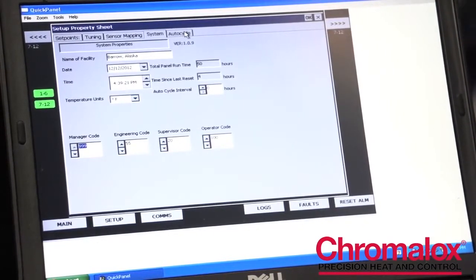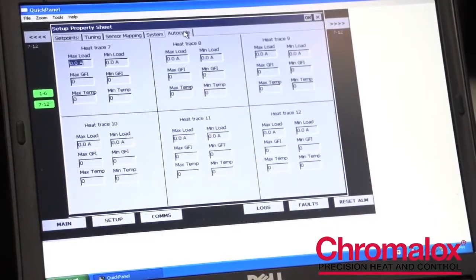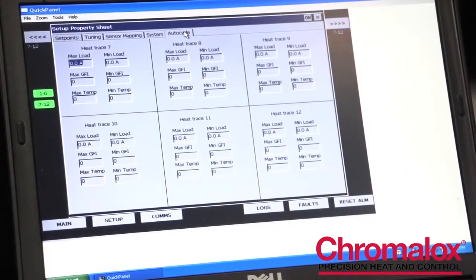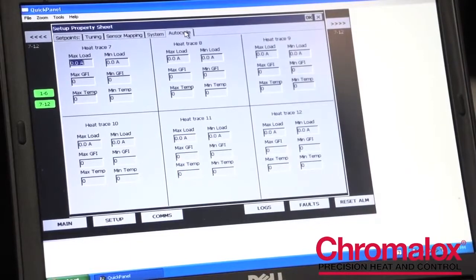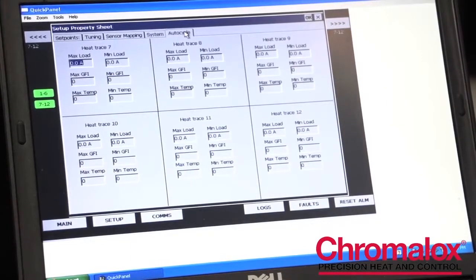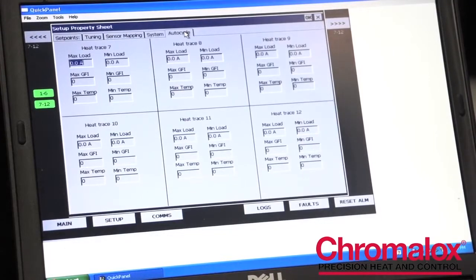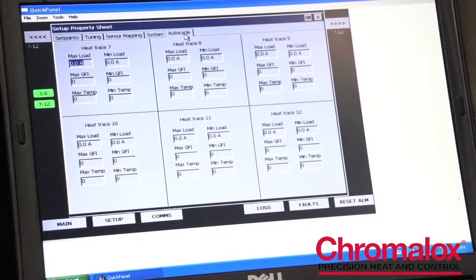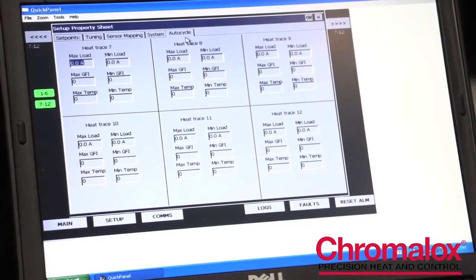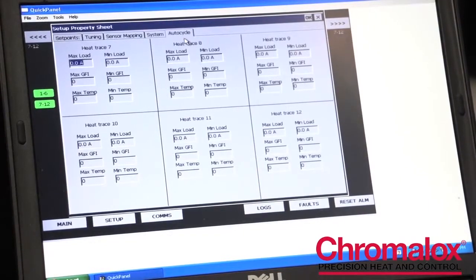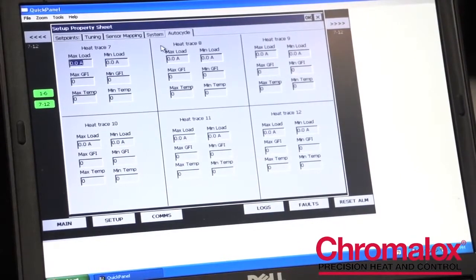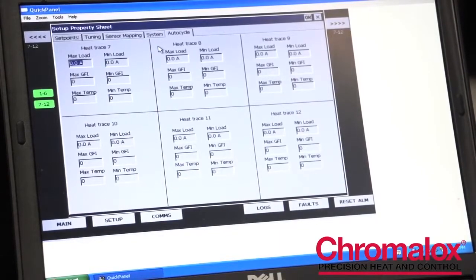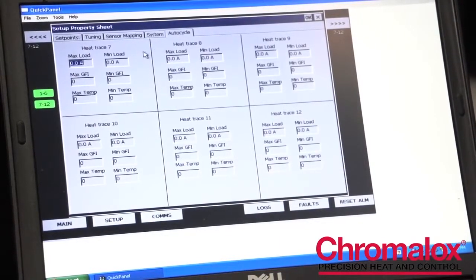The last tab is our auto cycle tab. This is a wonderful maintenance feature that's built into every ITLS panel, which allows the system to ping all of the different circuits, which enables the maintenance men to know whether or not they have an issue on any of the circuits. If you have a sensor that's failed or you have a high current situation, you will receive an alarm, and you can service it during down times so that your system is ready to go when you need it to perform.